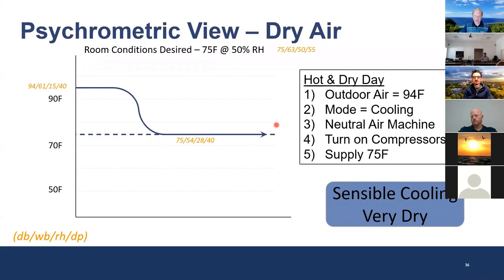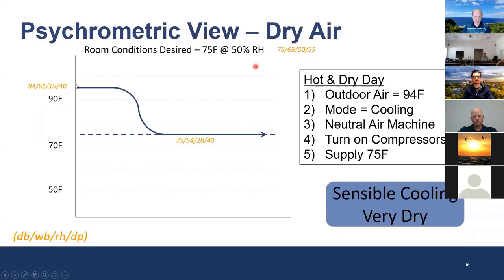From a psychrometric view: the key variables are dry bulb, wet bulb, relative humidity, and dew point. In the top left of the chart, take an outdoor condition of 94°F dry bulb, 61°F wet bulb, 15% RH — that's a 40°F dew point, a real condition for Prescott, Arizona. The desired space is 75°F at 50% RH, which is a 55°F dew point. We take that hot air, recognize we're in cooling, turn on compressors, drop it down to 75°F neutral air — and note the dew point stayed fixed at 40°F. The moisture content didn't change; we just got the temperature where we want. We're still very dry at 28% RH. That scenario doesn't apply to the Southeast very much.